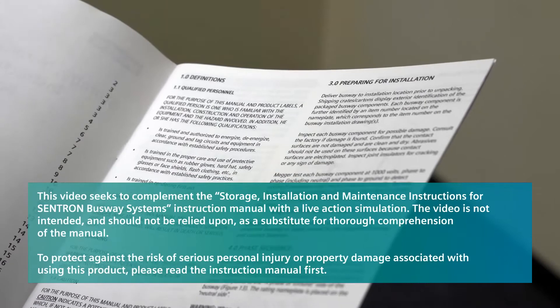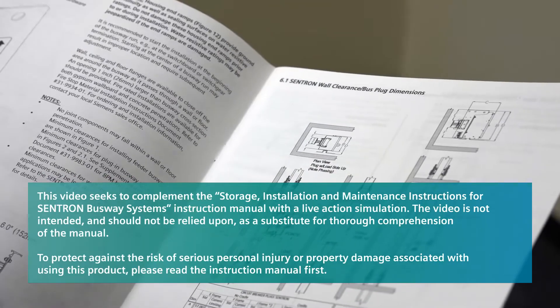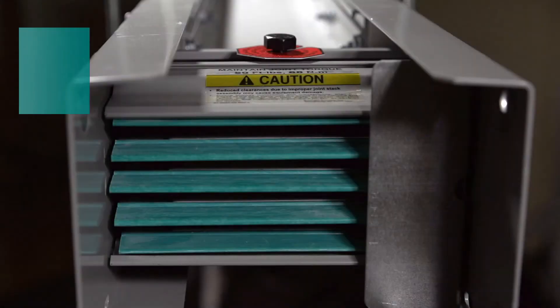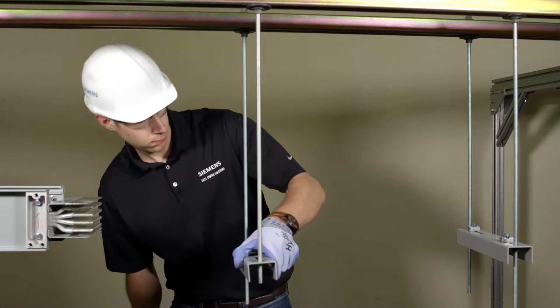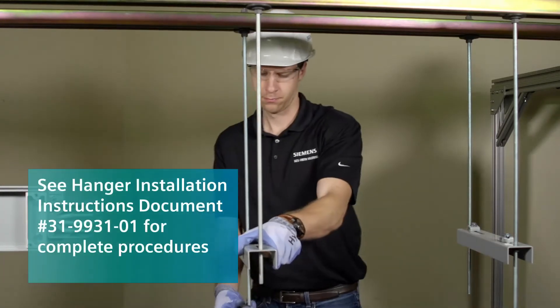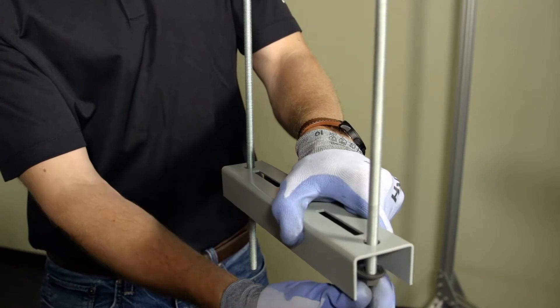Throughout the installation, make sure you use the SENTRON installation and maintenance instructions for reference, beginning with Section 7.0. Trapeze hangers and single drop-rod hangers are used to support horizontal busway, as long as the spacing between the hangers is 10 feet or less. The required half-inch steel drop-rods and hardware is furnished by the installer.